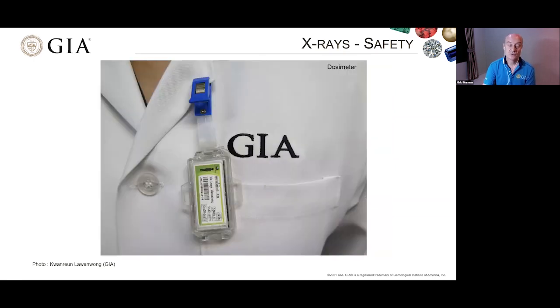In addition to the signs, we have dosimeters as well, and training is very important too. So every staff member wears one of these personal film monitors and is sent to be checked for any radiation exposure each month. Different countries have different regulations regarding safety, and some, like our Bangkok and Carlsbad locations, require all or some of the staff to sit examinations, while in New York, there is an annual safety inspection and a course that has to comply to local regulations.